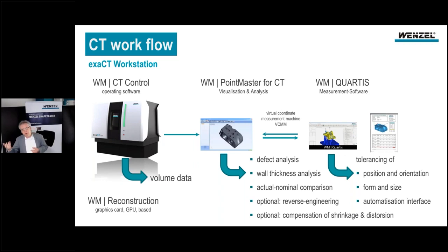We call this virtual coordinate measurement, VCMM, for the machine. Therefore we communicate with the Point Master, and then we have in addition the possibility of tolerancing, positioning, orientation, form and size, and this is our automation interface for a fully automated process. So this is the CT workflow.